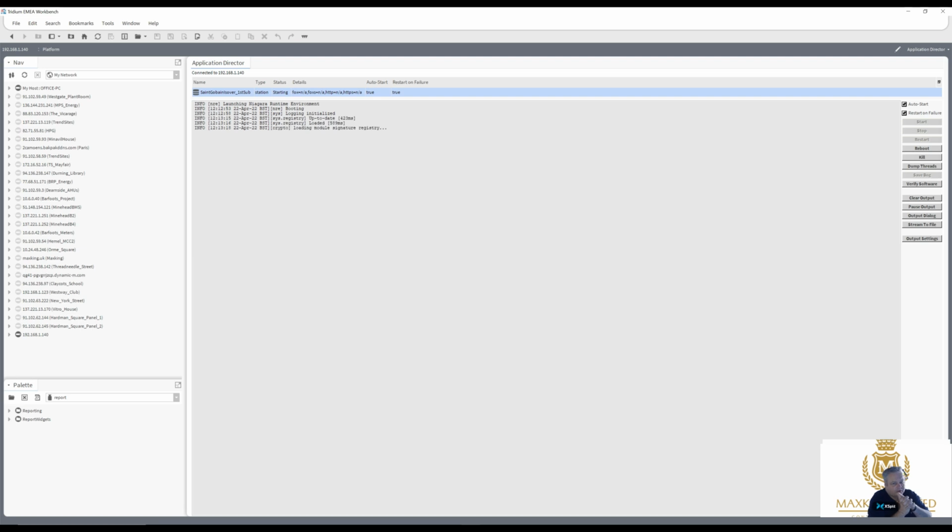So we changed the config.bog to config.zip, we unzipped it, we went into the XML file, we removed anything that had ftpReport, saved it, put it back to a zip, renamed the zip to a bog, loaded it onto the AX station, made a backup in software, and then we had a disk file.